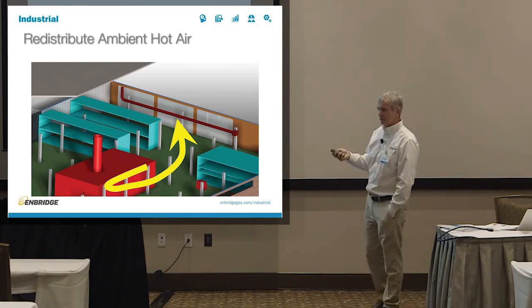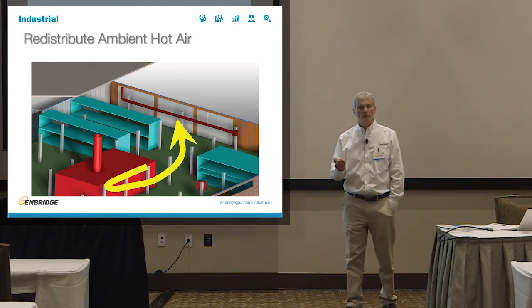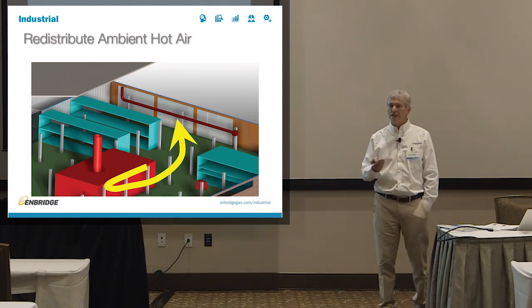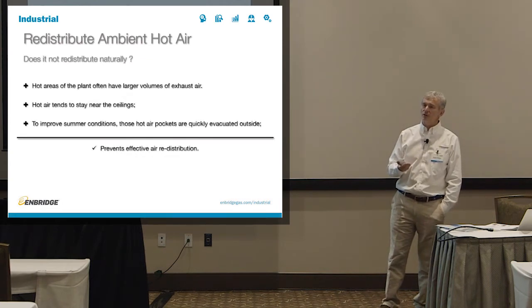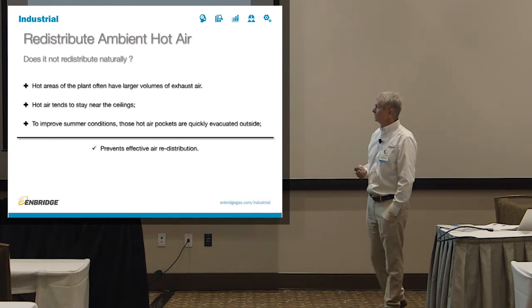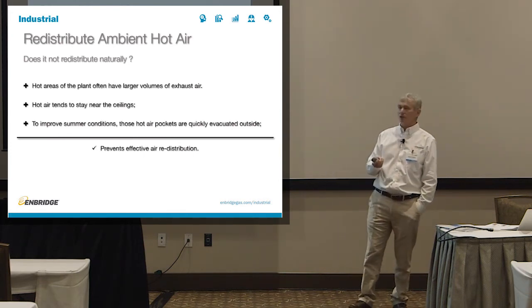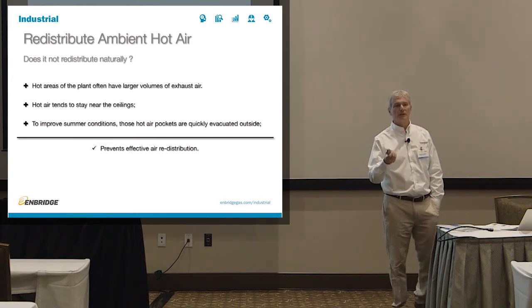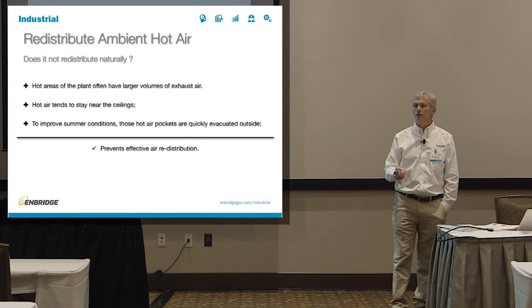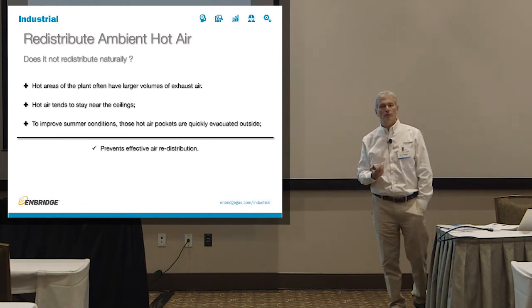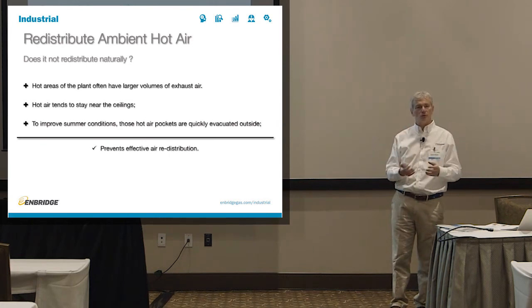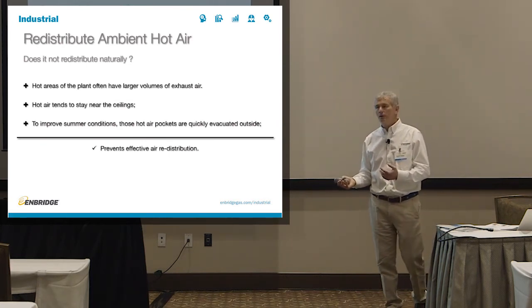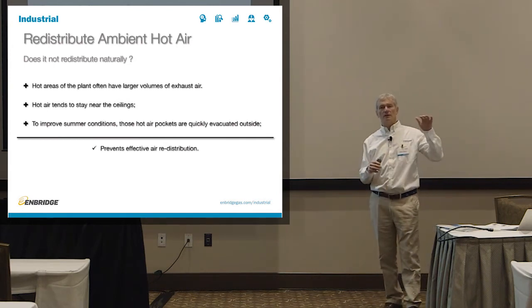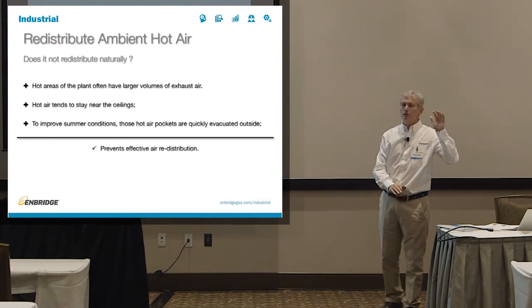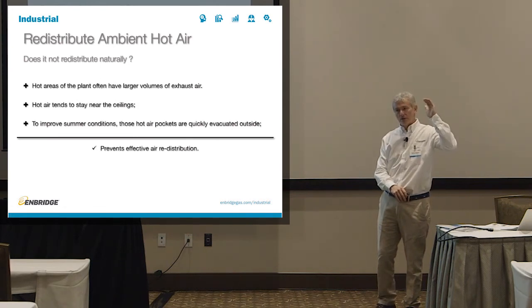And when we suggest that, everybody says, well, it just redistributes naturally. But that's not the case. In 95% of the cases, that is not what really happens, and there are a number of reasons. One is hot areas of the plant will have large volumes of exhaust air. Because what happens in the facility when people start complaining in the middle of the summer that they're hot? You usually put another exhaust on your roof to get that heat exhausted as fast as possible so that people don't walk out because it's too hot to work. Hot air tends to stay near the ceiling, just like in your house. Near the ceiling is nice and warm, your feet are usually cold. Same thing in the facility. So it doesn't do you any good if all the heated air is up near the 30-foot ceiling.